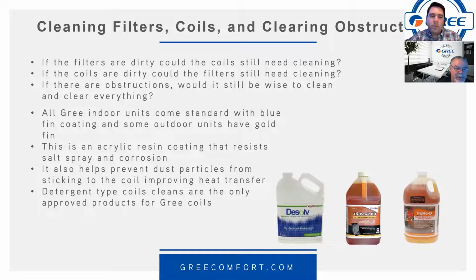But you should only use a detergent when you're cleaning these coils. Don't use an acid that could etch away some of that acrylic resin coating. There's a bunch of different brands out there. This is a Rector Seal product that's been designed for cleaning mini splits. Nu-Calgon has Tri-Power. This is Diversitech Triple D. These are all concentrated detergents, and they will do a good job at removing some of the dust and dirt without damaging that acrylic resin coating.